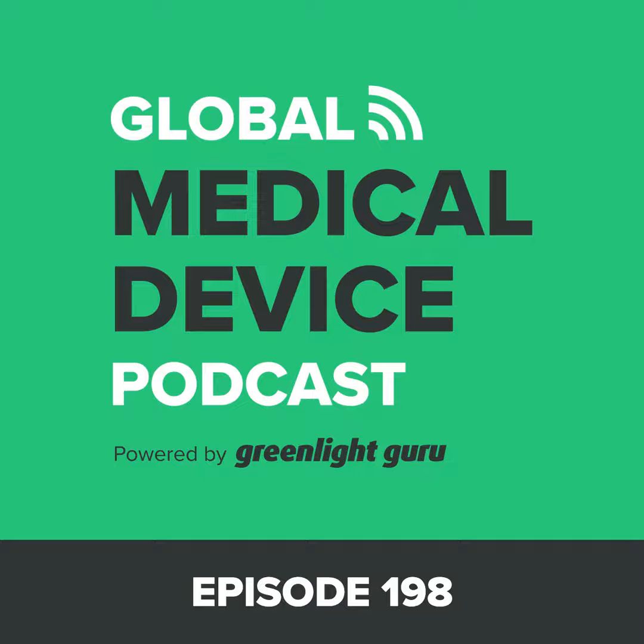Sure. Going back to my example of the blood glucose meter, that information has to be crystal clear, because the user population in that case could be a child, could be an elderly person, could be somebody with good eyesight, could be somebody with poor eyesight. But they have to know what that means. Because if I misinterpret and take the wrong action, that could lead to death. So this is an example where an IVD product is not without risk. But even within the lab environment, even if it's CLIA waived, there's still risk. It has to be clear to that person what that means.